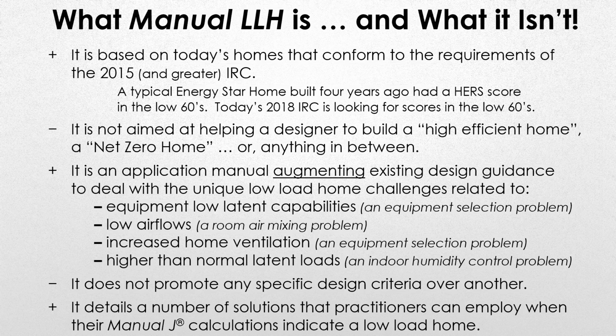The manual's not aimed at helping a designer build a high efficiency home or design a high efficiency HVAC system or a net zero home or anything in between. It's basically an application manual that augments existing design guidance to deal with the unique low load home challenges related to equipment, low latent capabilities, low airflows. You're going to have room mixing problems, increased home ventilation in some cases, and higher than normal latent loads. It doesn't promote any specific design criteria over another.